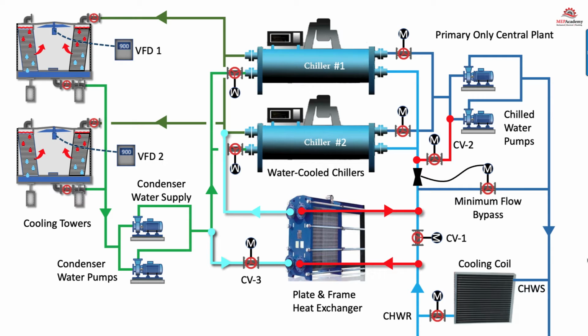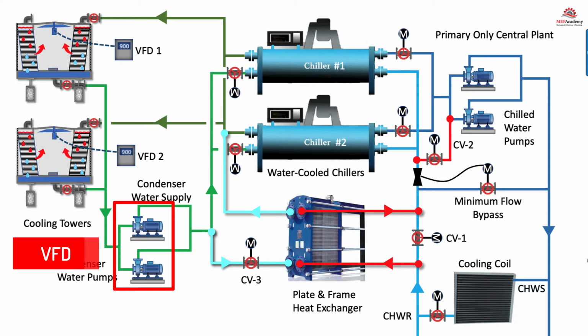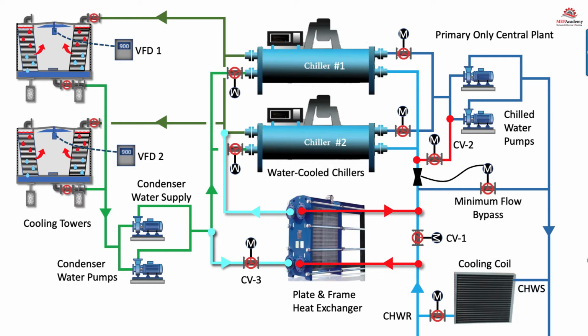At the same time, the condenser water pump can reduce its speed and water flow with the use of a variable frequency drive, VFD, to compensate for the reduction in demand on the chiller because of the economizer, if the minimum flow is maintained through the chiller. When the chiller is at partial load in an integrated economizer system, the condenser will require the manufacturer's required minimum flow for head pressure control. The cooling tower will also have a requirement for minimum flow that will need to be adhered to.